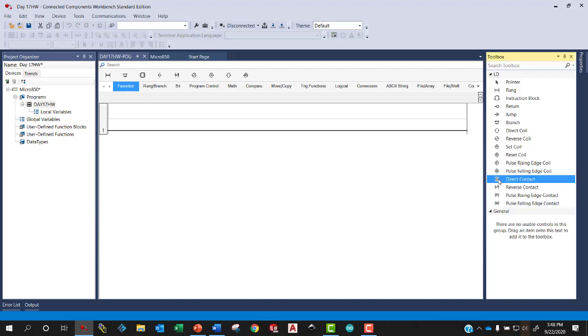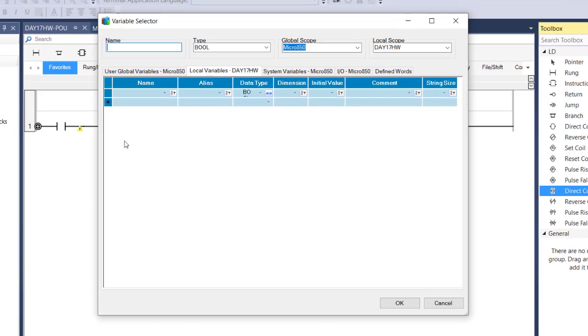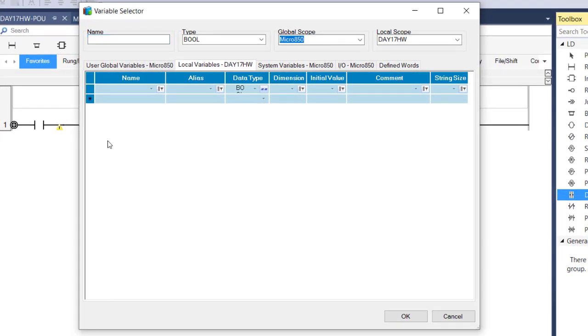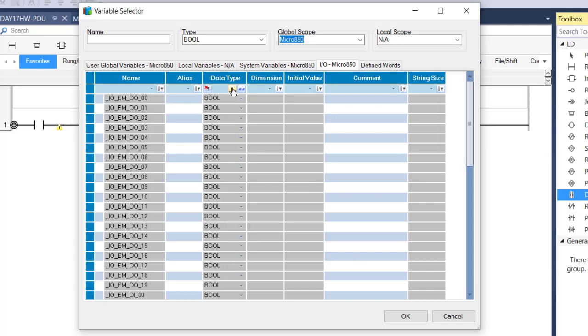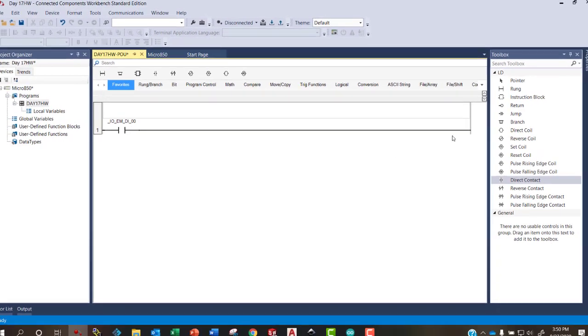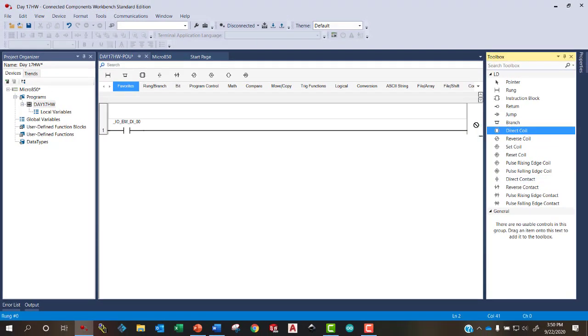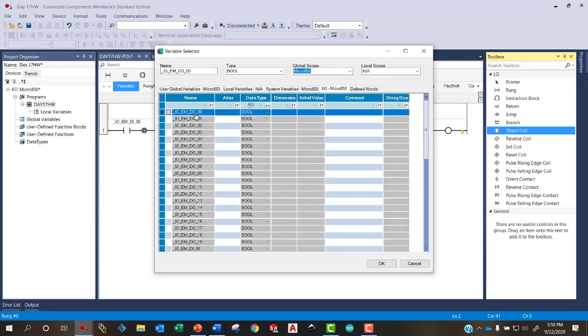Let's grab a direct contact, drag it into the Ladder. We're going to hover it over the plus sign at the beginning of this positive rail. And now this window automatically pops open that allows us to assign that direct contact to either a global variable, a local variable, system variable, or an I.O. point on our Micro 850 PLC. And if you're not seeing any of the Booleans, you might have to filter and say, show me all the Boolean I.O. points on the Micro 850. And it lists the outputs first. DO is Digital Output. And then down here it begins Digital Input. It starts with Digital Input 00. So let's pick this one and hit OK. So now this direct contact is associated with Digital Input 00 on my PLC.